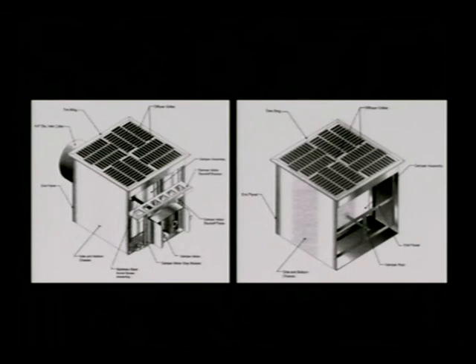They've changed that design. We ended up with these. They had some construction issues where the worm drive, that gets supported on the end panel, was a little too high, and as a damper came across, they would jam at about 50% open, and the worm drive motor is very powerful.